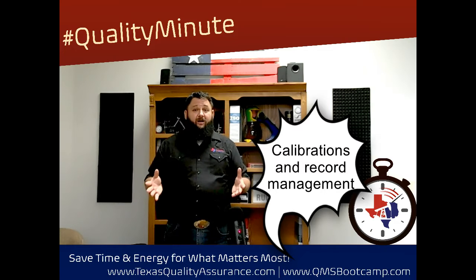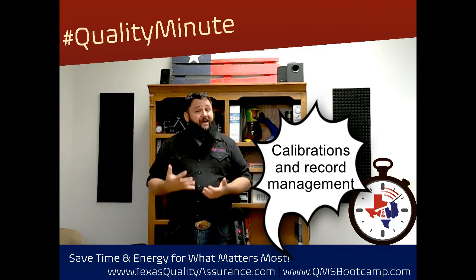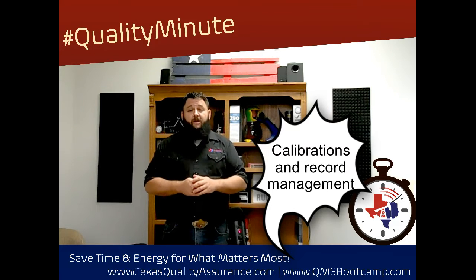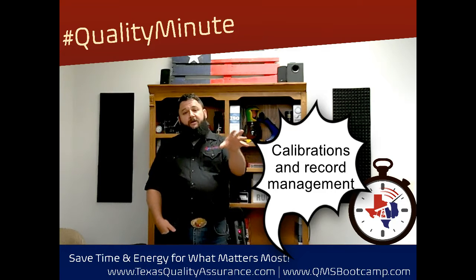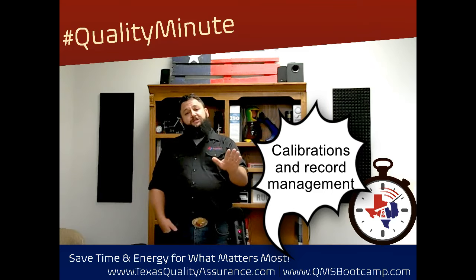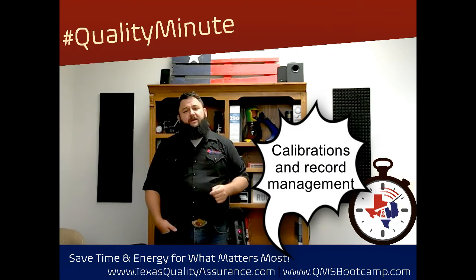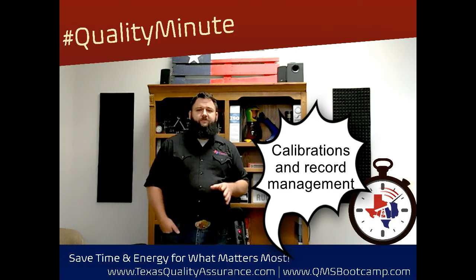Now, because these blocks stay in one place and they're not subject to a lot of wear and tear, you can put these on a 5-year recalibration or certification interval. And truth is, there are companies out there that will send a van out to your facility. They'll acclimate the temperature and humidity to the blocks, and then they'll check them, and you never even have to send them out. And you have very, very limited downtime in your production management system. So it works wonders for you.